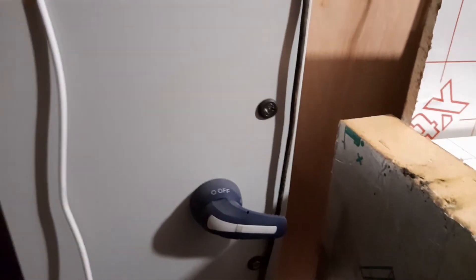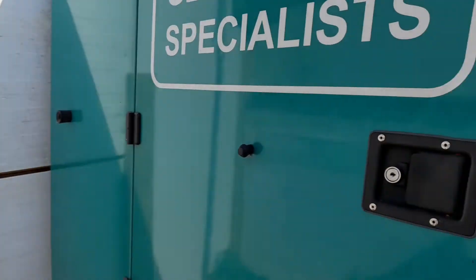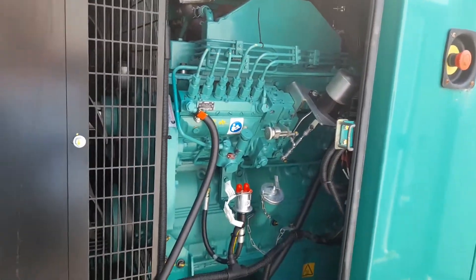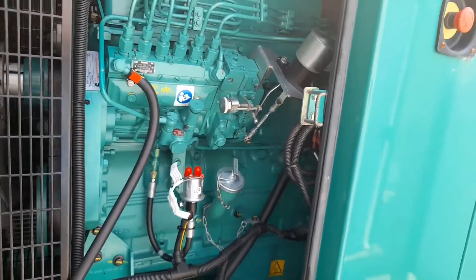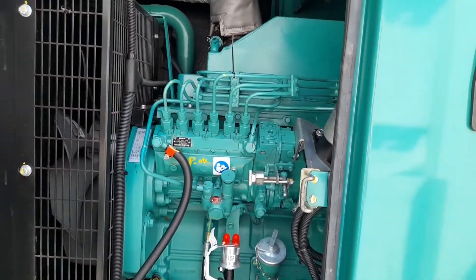The final form of redundancy is this giant big box here. As you can see, it's an on-off switch — that's a giant breaker for our big generator. Inside the little box I've built for it, out of old fridge panels, we have the big generator. This is a massive generator — it's overkill for what we need — but again, I'm a believer of get more than you need. So I've got a bigger oversized generator, and when it is on, the inverters are working full bore charging. This thing's barely on tick over, so we're using not a lot of fuel at all to get a charge on our system when we don't have the solar coming in.